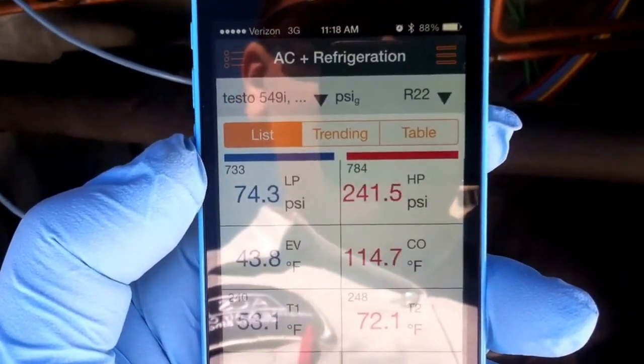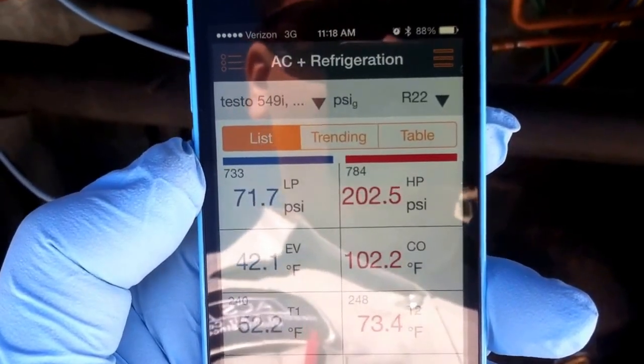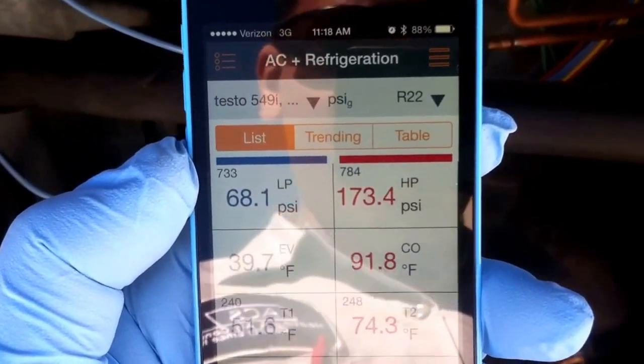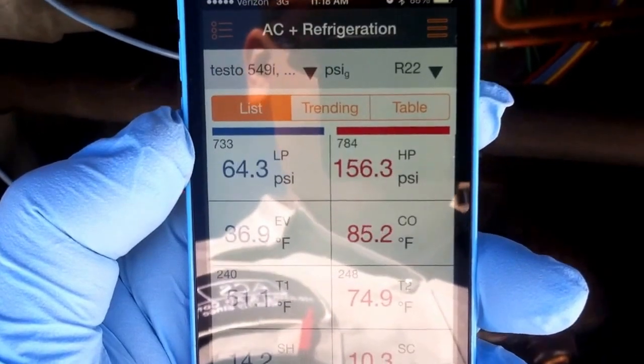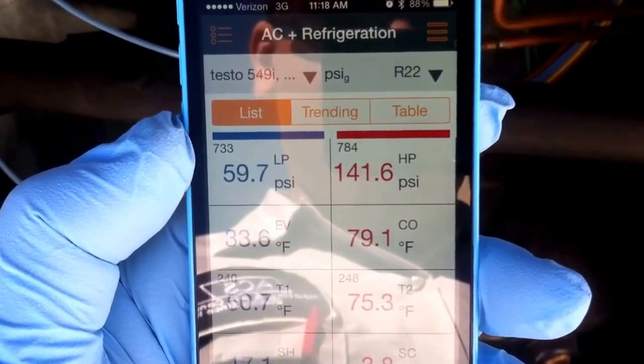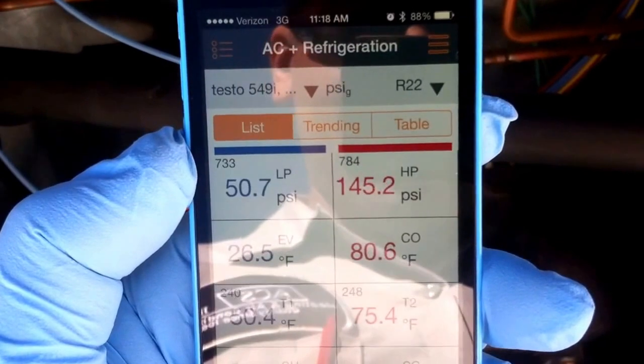Still a little chilly outside. The low ambient control keeps cycling the fan on and off. The head pressure will go down, get to about 145, then kick out the fan back up to about 270.